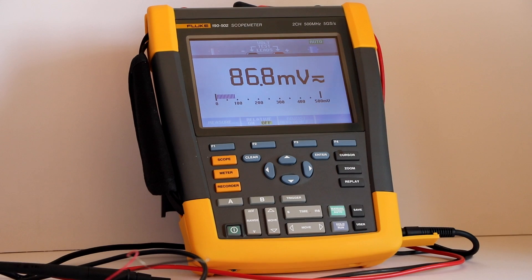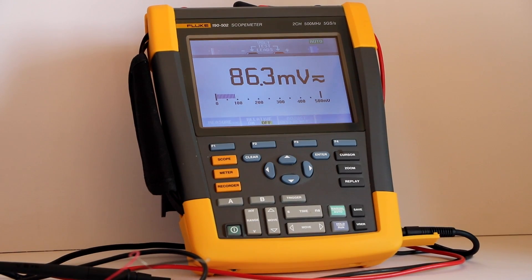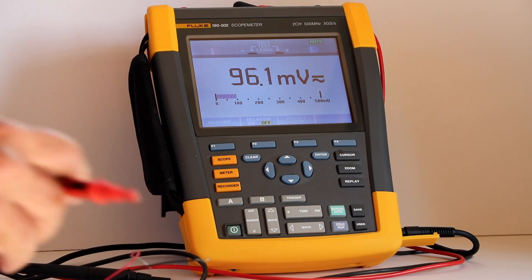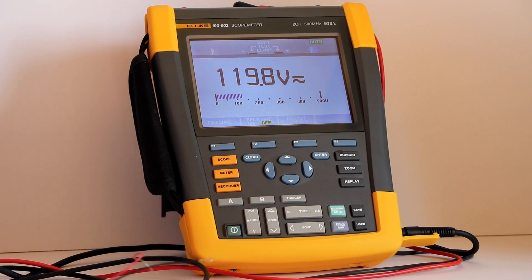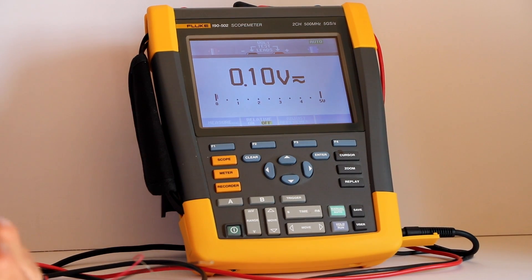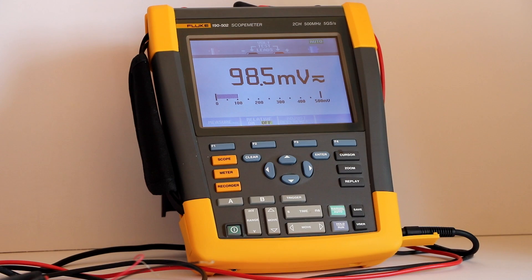Measuring AC utility voltage, the reading must be within normal range. Notice that the voltage is 119.9 volts, which is normal for a utility voltage. Next, we'll insert a 10-to-1 attenuation probe into the outer oscilloscope analog channel BNC input port.